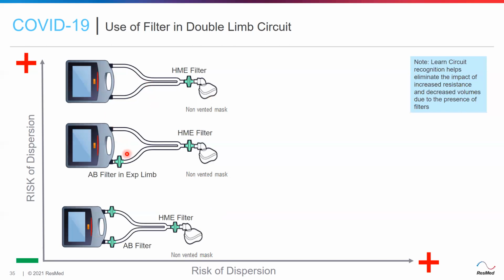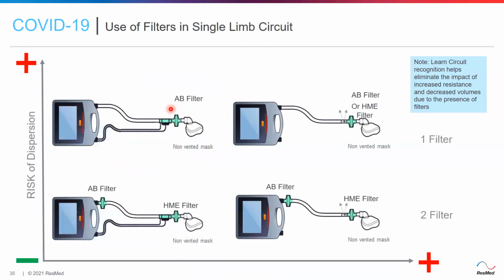The thing that we need to keep in mind is that whenever we are using filters in a device, there is a feature in the device called learn circuit. Learn circuit. Fine. So we need to run learn circuit whenever we are using different types of filters with the device, so that the device knows the kind of resistance that is there in the various limbs, and accordingly it will adapt to overcome that resistance, since these filters would pose resistance to the airflow. Fine. So that is why learn circuit needs to be used whenever we are placing filters in the circuit. Fine. So this is about the dispersion risk in the single limb circuit.